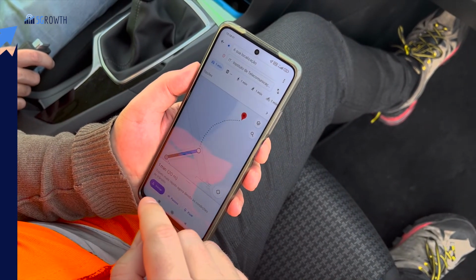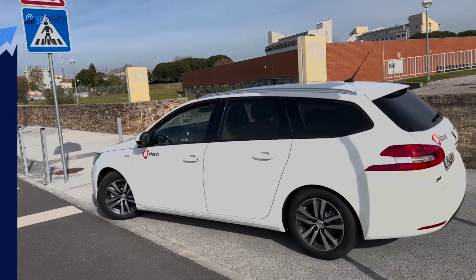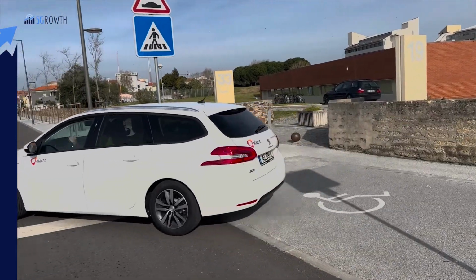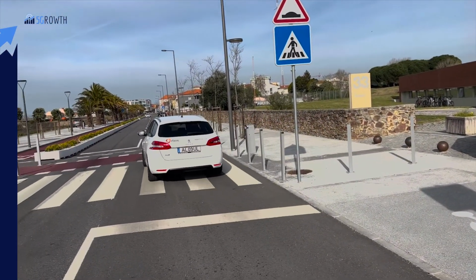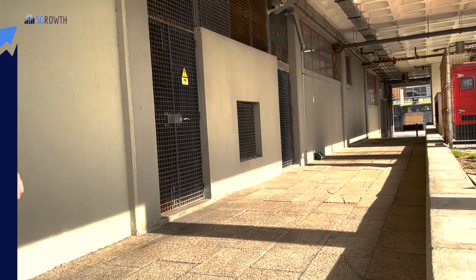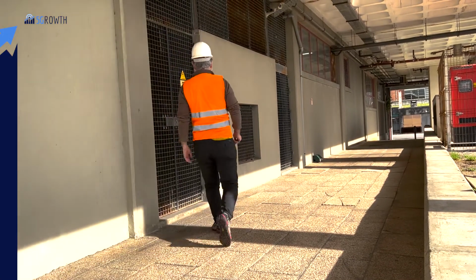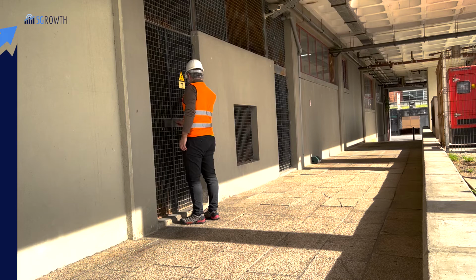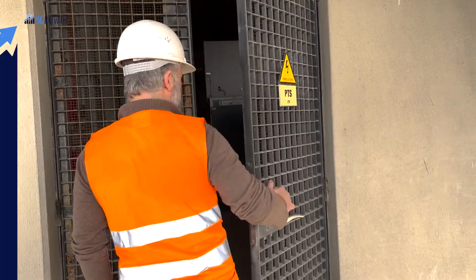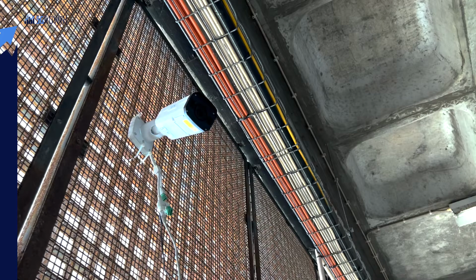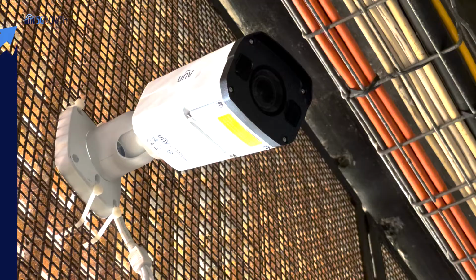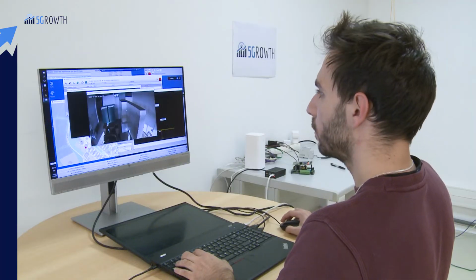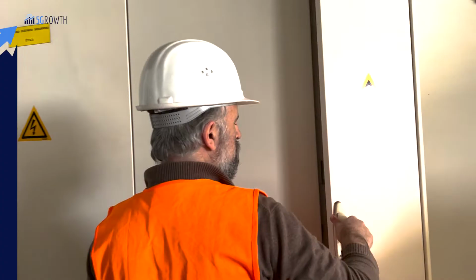The team can use the geolocation of the secondary substation to establish the better route to get there. When the team enters the substation, the intrusion detector is actuated. The detector signal is acquired by the substation controller and immediately transmitted to the control center, showing in the operator workstation. That blinking door is telling the operator that something requires his immediate attention.